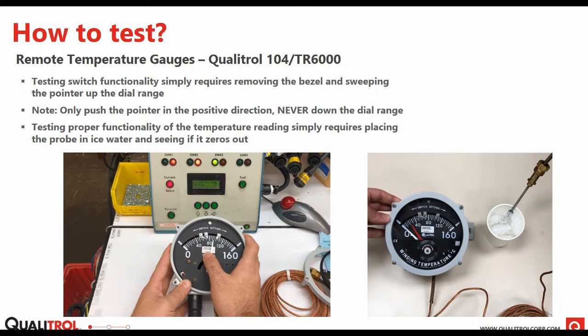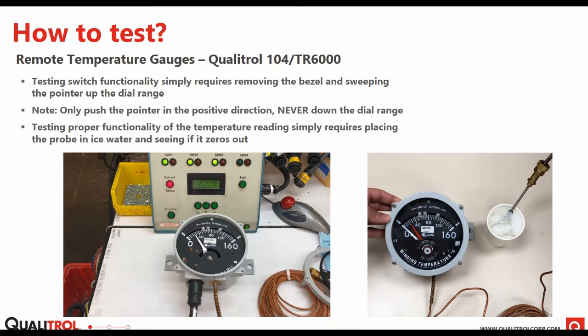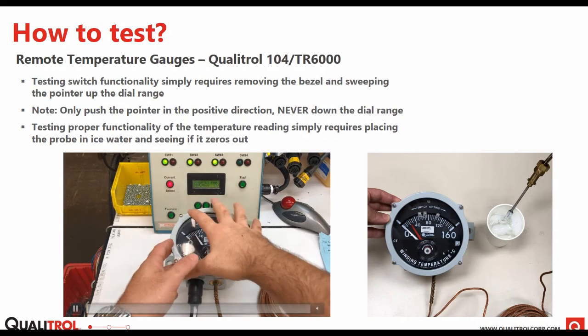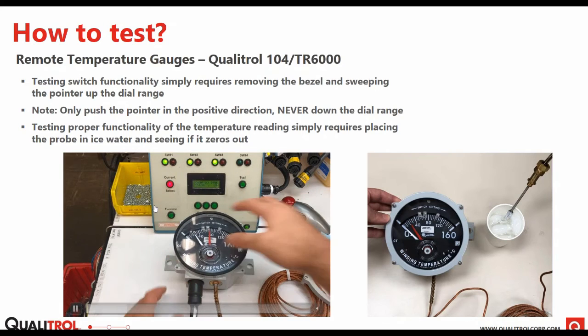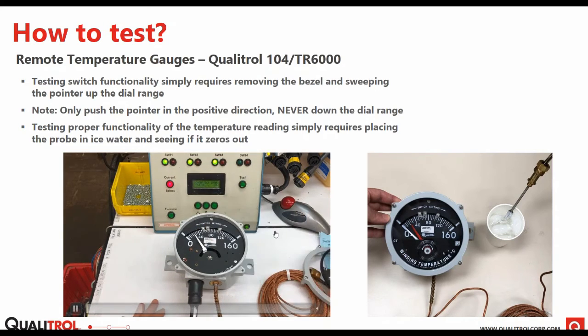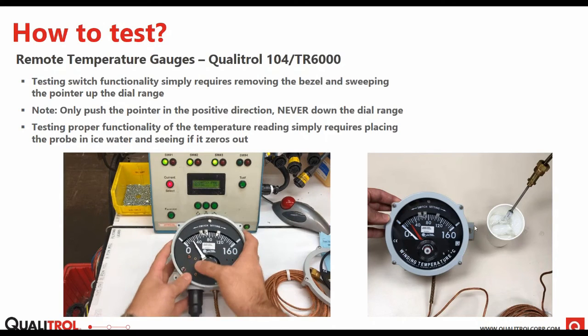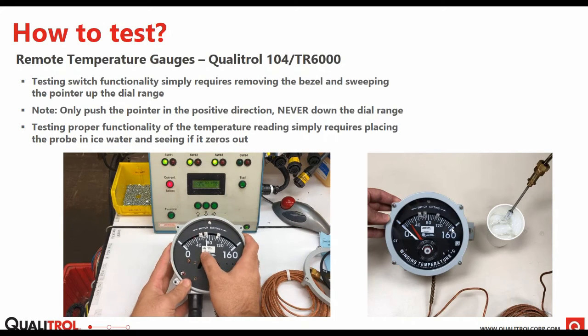You could pull that probe out of the well, put it in a cup of ice water, and watch the gauge go down to zero. So these are two easy field tests that can be done on the 104 or TR6000 that we offer. This ice bath test can also be done on direct mount bimetal thermometers. Pushing the pointer cannot be done on those.